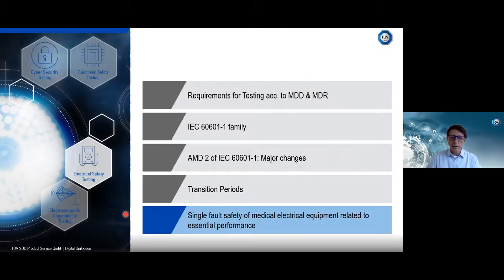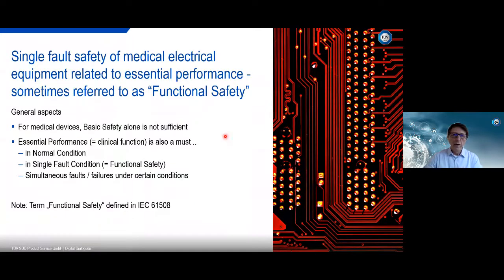Good. Last but not least, I would like to give you an insight into the single fault safety issue of medical devices relating to essential performance. Some general aspects at the beginning: for a medical device, basic safety alone is not sufficient for a product, so we also have a so-called essential performance, which is basically a clinical function. This essential performance must be valid in normal condition, in single fault condition, and also when simultaneous failures occur under certain conditions. So in theory, we sometimes call this single fault condition for essential performance functional safety, although this term is defined in 61508, which is not applicable for medical devices. We took this term as well for this aspect.